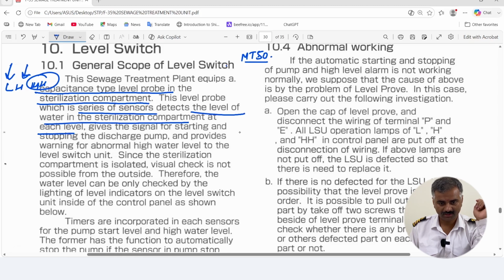You see here, in a capacitor, Q is the charge, which equals C, that is the capacitance value, multiplied by voltage V. If you keep the voltage constant, which in our case is around 24 volt, that you give a fixed voltage to the probe, so the voltage signal is fixed. What changes is your Q. Q changes with change in capacitance. If you differentiate, dQ by dt is equal to I. So that shows that capacitance is directly proportional to current. So as capacitance changes, your current changes.